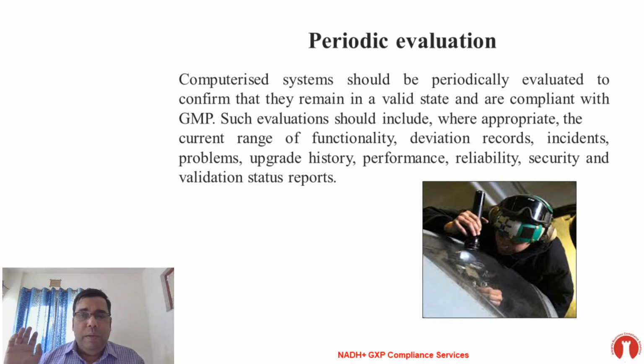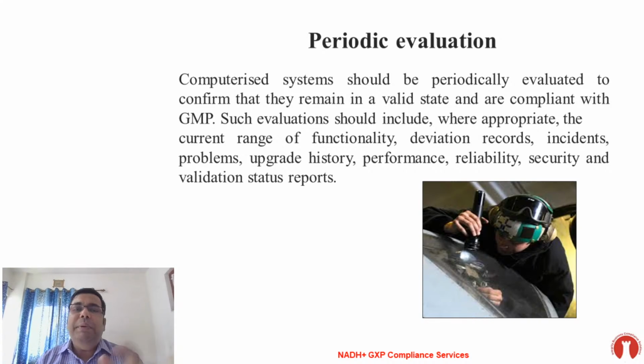But many companies and many people consider that audit trail review is only the review of the computerized system audit trail. No, audit trail means the reconstruction of all the events. All the events which are not supported by the computerized system, such as sample preparation, standard preparation, dilution, sonication, should be reconstructed along with the computerized audit trail. That is actually the review of audit trail. Many people ask me this question also. I think I shared this information in the last training, but let me share it again.